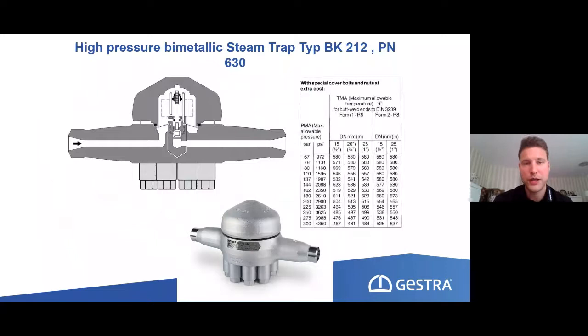So I told you bimetallic steam traps are very much suitable for high pressure applications. This is what a BK looks like when we go, for instance, to power plants, where we could have pressures up to pressure rating PN 630. So this kind of steam trap will work up to maximum pressures of 300 bar, which is quite a lot, and up to differential pressures of 250 bar.